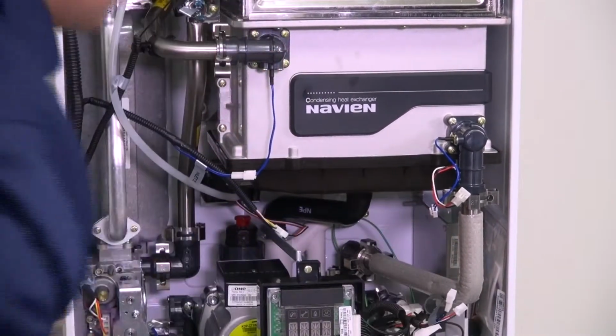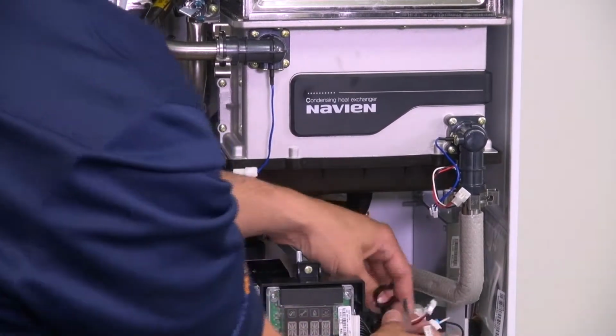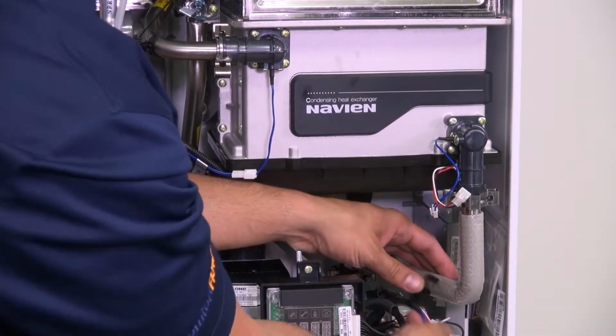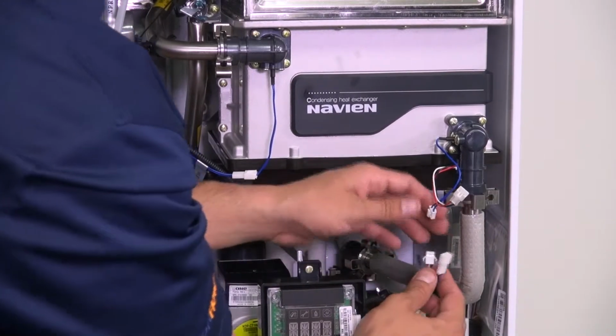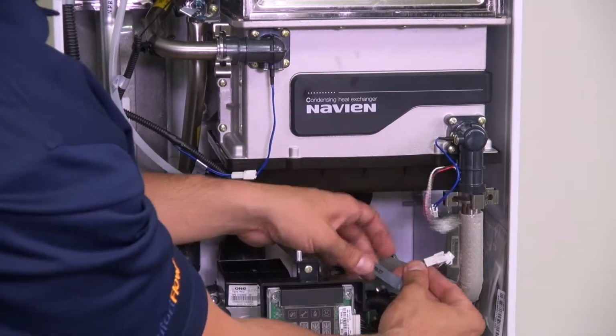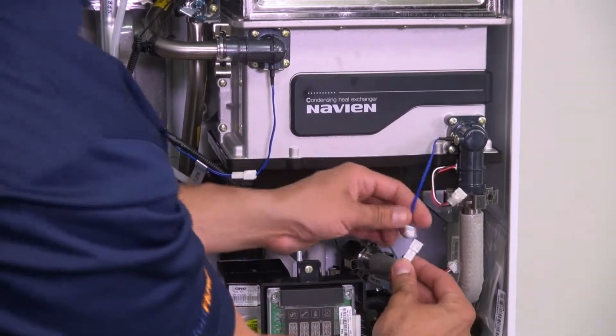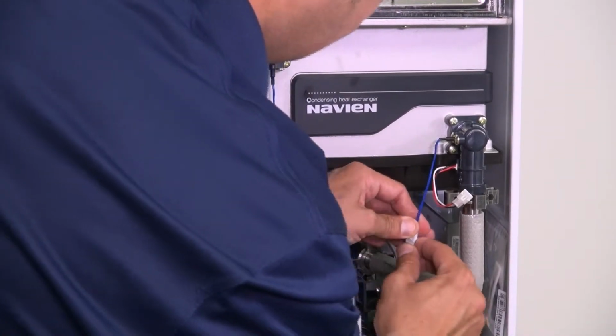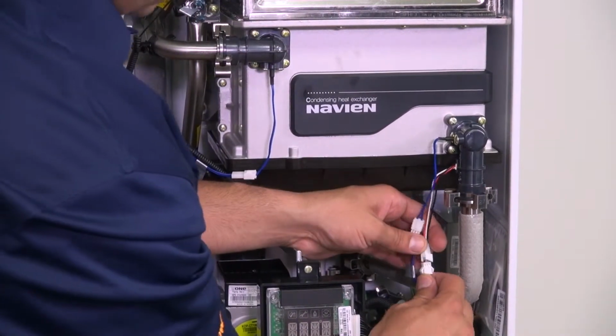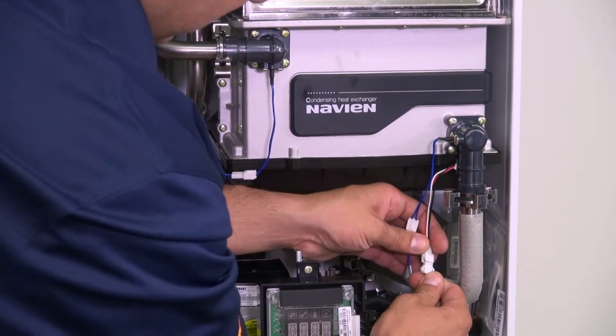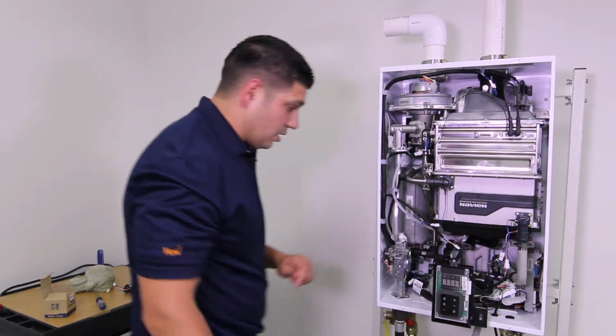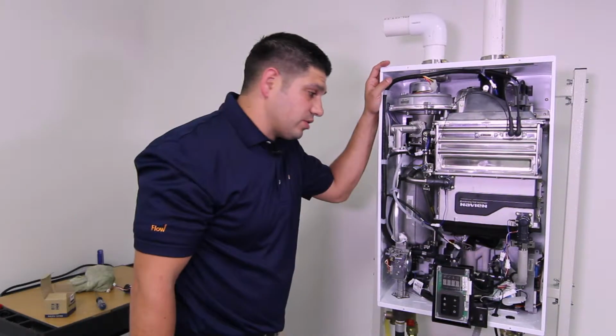And that's properly set in there. For my wiring harness, there is a little clamp here that fell off. Then we got our 2 wires. We got our inlet wire, which is for our inlet thermistor. Just go ahead, it just gets clipped in, and your flow sensor wire. So that will complete the installation of our flow sensor.